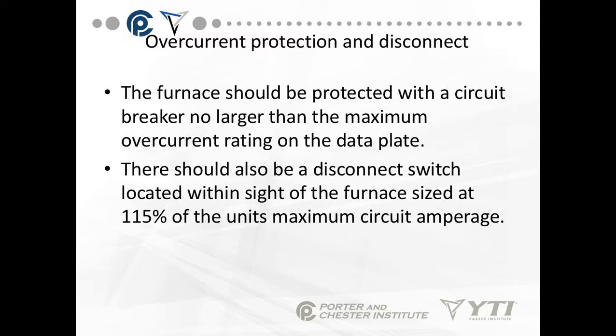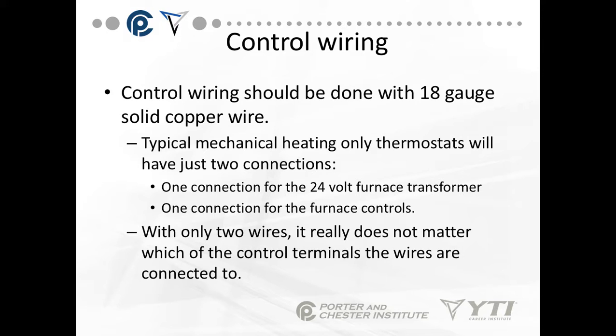The furnace has to be protected with a circuit breaker no larger than the maximum rating on the data plate. There should also be a disconnect switch located within line of sight of the furnace that's rated at 115% of the unit's maximum circuit amperage. Control wiring has to be done with 18 gauge solid copper wire. Typically, mechanical heating only thermostats will have just two connections. One connection for the 24-volt transformer, one connection for the furnace controls. With only two wires, it really does not matter which of the control terminals the wires are connected to because it's just a switch.